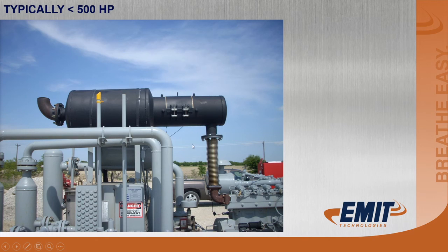Here's a common EAH housing, so it's EMIT accessible. It has a spot for 2 elements, and it's got a hospital grade silencing on it. 3306 package. Pretty common use of a housing. In this particular picture, the bellows are pretty long. We don't typically like to have bellows that long. Bellows that long will tend to break and crack prematurely.